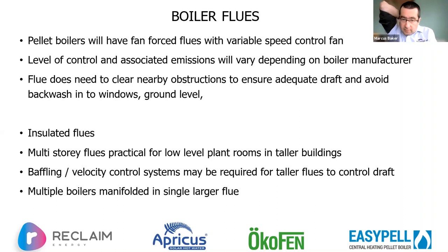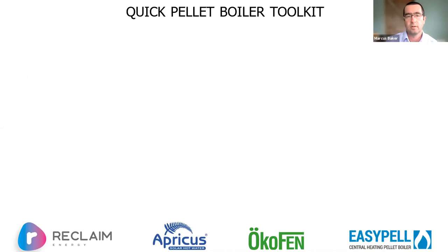The flue does need to clear obstructions to avoid backwash. Generally, they're going to be insulated. It's very practical to have multi-storey flues for tall buildings with a low-level plant room, like we saw at that project. That's only 6 stories, but I don't see why you couldn't go 20 stories. You just have to have some baffling and velocity control to reduce the draft, because we want the boiler ultimately to be in control of the draft through the flue and not for it just to be sucked willy-nilly. And we manifold multiple boilers into a larger single flue.